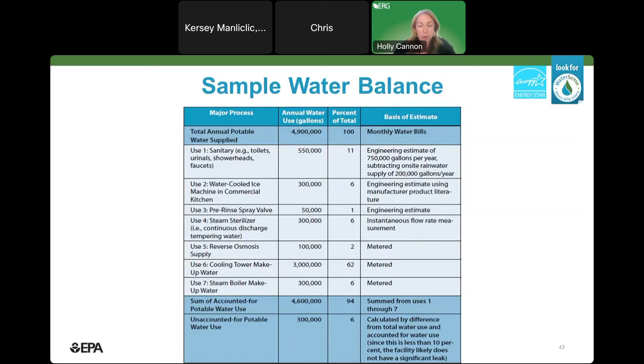You want to make sure you note the basis of your estimate—some engineering estimates, some flow rate measurements on site, some meter data, all combined to estimate where water is going at that facility. At this particular facility, there was only 6% unaccounted for water use. Since that's not greater than 10%, I can assume the calculations are fairly accurate—not perfect, but close—and there's probably not a major leak or something I missed.